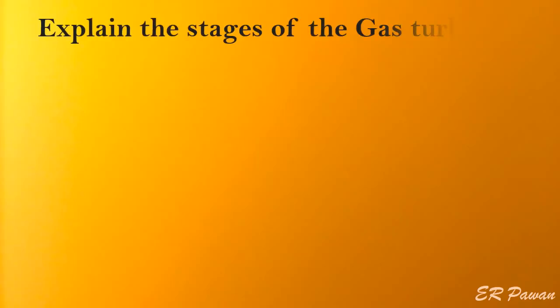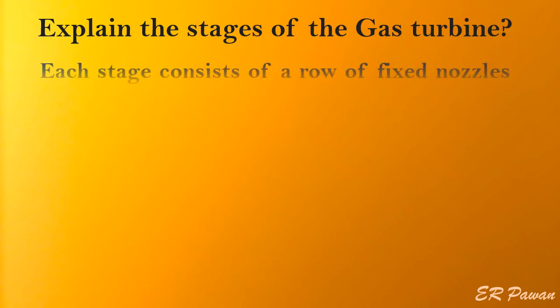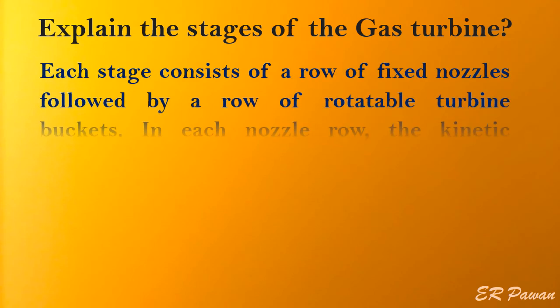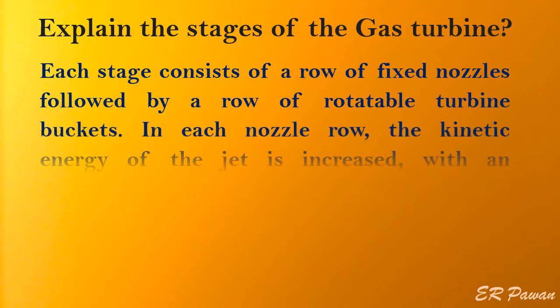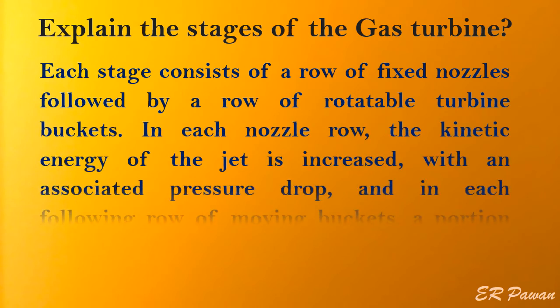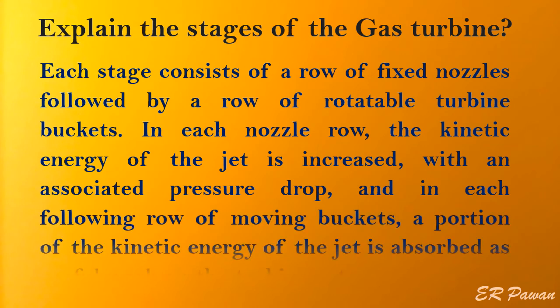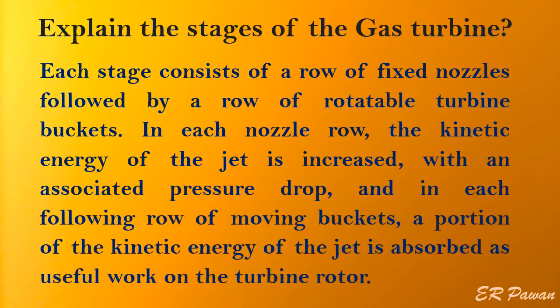Explain the stages of the gas turbine. Each stage consists of a row of fixed nozzles followed by a row of rotatable turbine buckets. In each nozzle row the kinetic energy of the jet is increased with an associated pressure drop, and in each following row of moving buckets, a portion of the kinetic energy of the jet is absorbed as useful work on the turbine rotor.